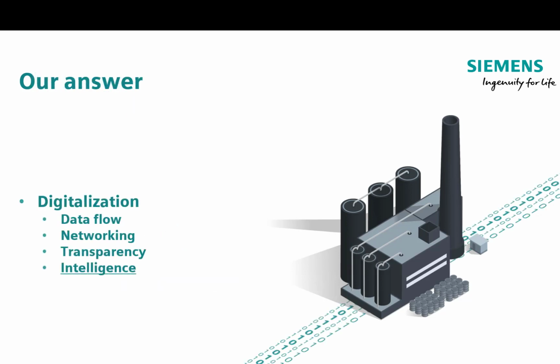If we have a look at the digitalization philosophy, now we've got this green cable in, we've got the network infrastructure to bring back copious amounts of data. We haven't got the bottlenecks associated with Profibus DP that we've had in the past. We can bring back more and more information from the field, but we don't want to increase the complexity of getting the plant up and running. This needs to come back on what is commonly referred to as a second data channel. That brings back the intelligence from the field, from the smart instruments, without affecting the top automation layer.